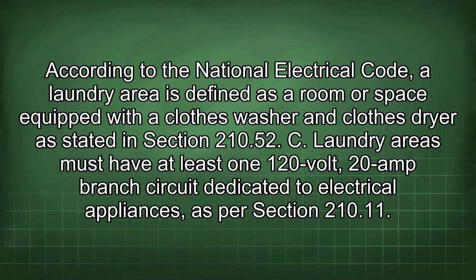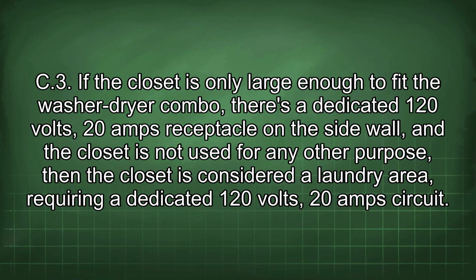According to the National Electrical Code, a laundry area is defined as a room or space equipped with a clothes washer and clothes dryer, as stated in section 210.52.C. Laundry areas must have at least one 120-volt, 20-amp branch circuit dedicated to electrical appliances, as per section 210.11.C.3.